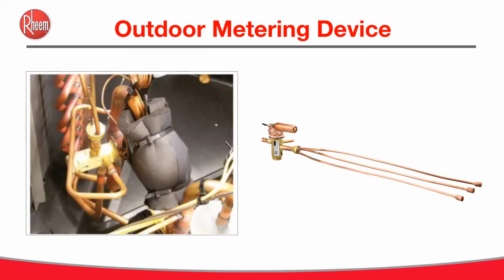Because as we know, superheat is a necessary evil. We need superheat. Why? Because we want to ensure we have 100% vapor. If you have no superheat, you can't guarantee that you're sending vapor to the compressor. And we know what happens when you send liquid to compressors. They don't like it. It doesn't matter if it's a scroll or what type of compressor, it does not like liquid.